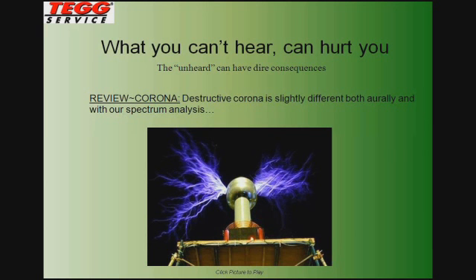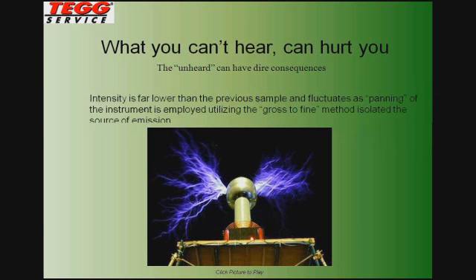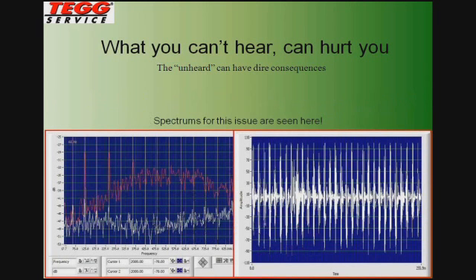And when those additional elements are superimposed on the naturally occurring corona, you get a different type of spectrum, which can be seen here. And the key thing is we begin to lose in the frequency analysis those 60 hertz fault frequencies we saw with the nuisance corona. They begin to disappear or get masked due to the discharges that are occurring now at non-uniform times on the sine wave. So we're back to what looks like tracking.